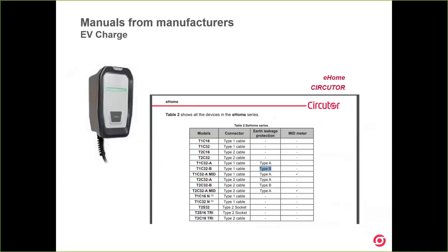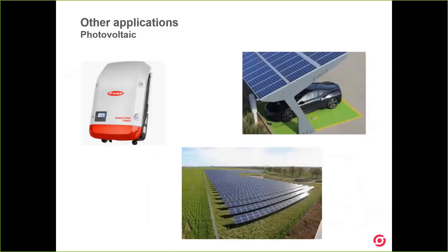In some other applications, I looked for manuals specifying type B solutions for inverters used in photovoltaic applications. To be honest, I didn't find it stated explicitly, but I think it's common sense that the most proper type of RCD for that kind of application should be type B as well. We have seen that type B solutions are referenced in most manuals for these kinds of loads. In case we need to protect a load, it's clear: we need to see the manual.